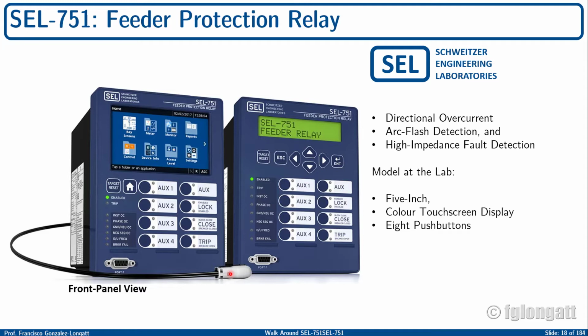Okay, we are talking about a very important feature for safety at distribution systems. But also this device is equipped with modern technology that is able to have very sensitive protection for earth fault, including high impedance fault. Okay, and this device has the possibility of detecting in a very precise fashion neutral currents of 200 milliamps.